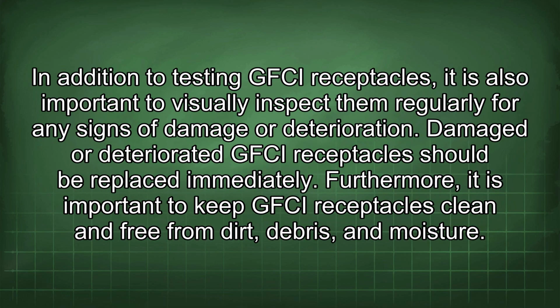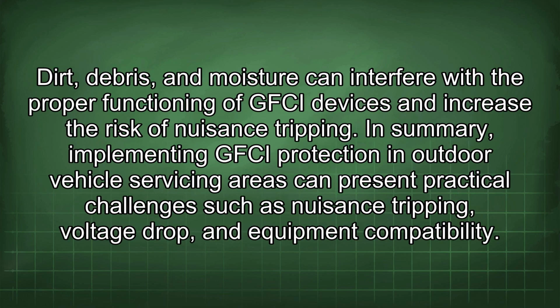In addition to testing GFCI receptacles, it is also important to visually inspect them regularly for any signs of damage or deterioration. Damaged or deteriorated GFCI receptacles should be replaced immediately. Furthermore, it is important to keep GFCI receptacles clean and free from dirt, debris, and moisture. Dirt, debris, and moisture can interfere with the proper functioning of GFCI devices and increase the risk of nuisance tripping.